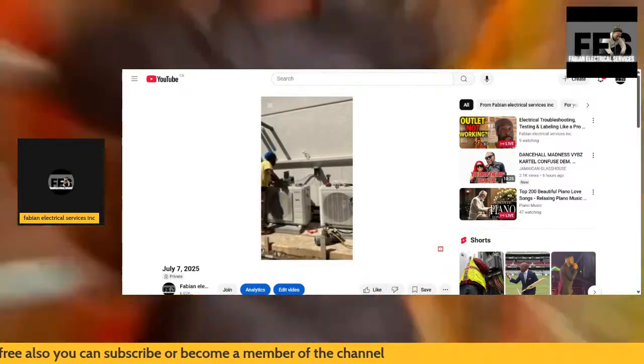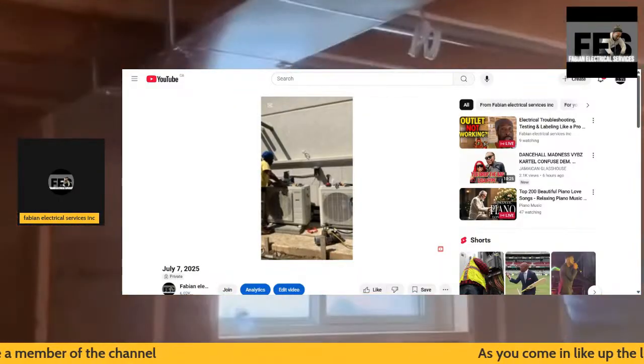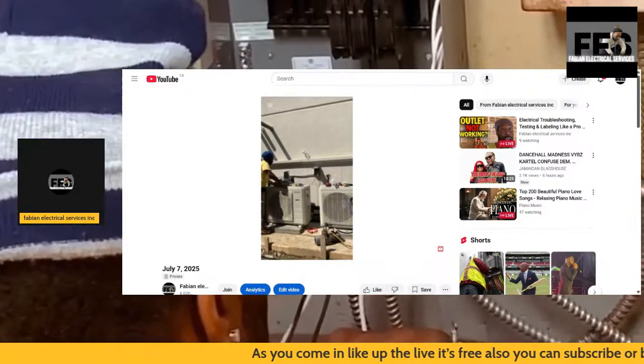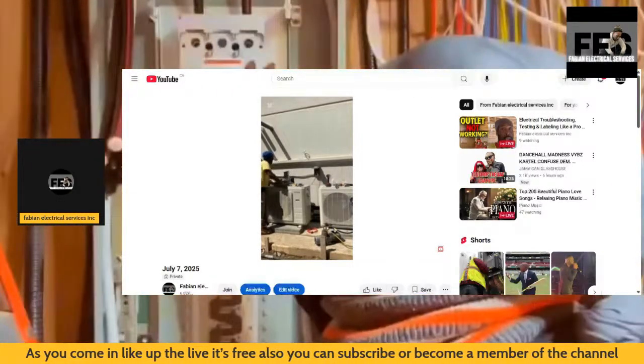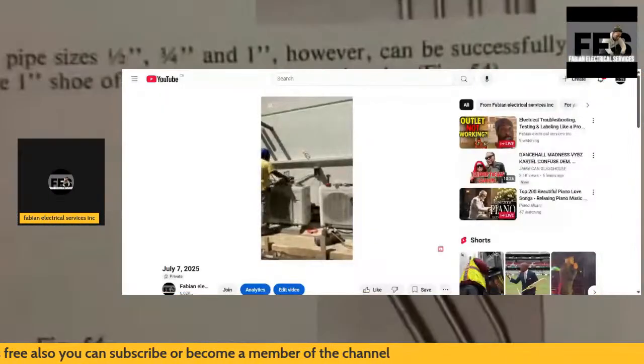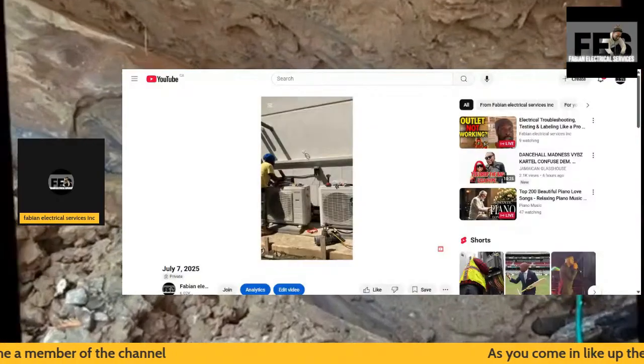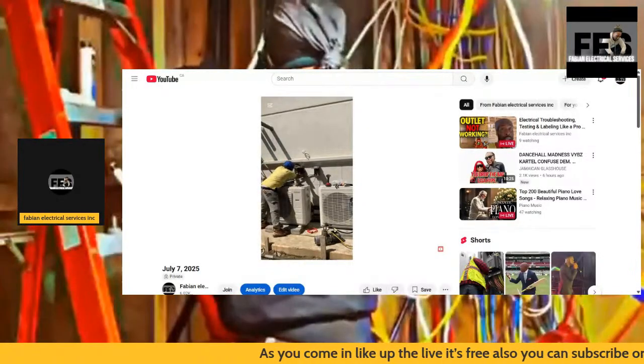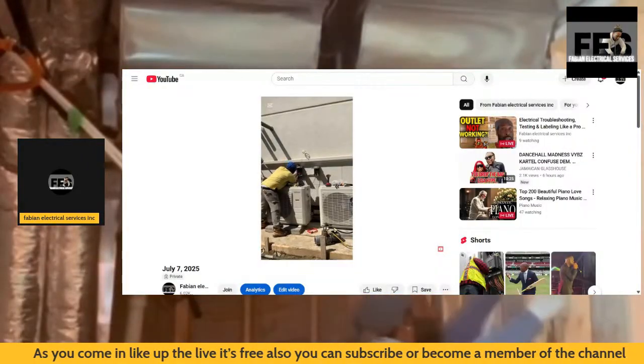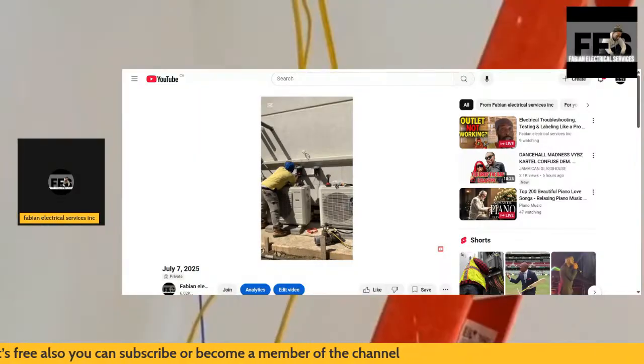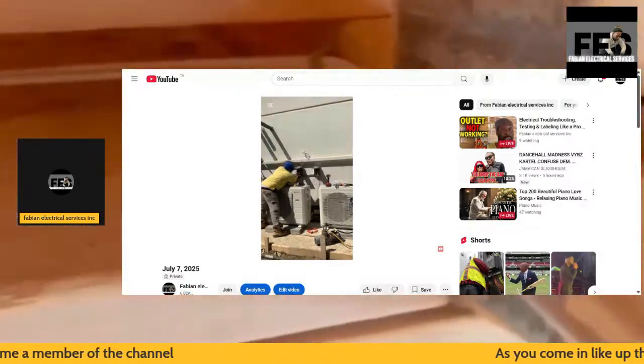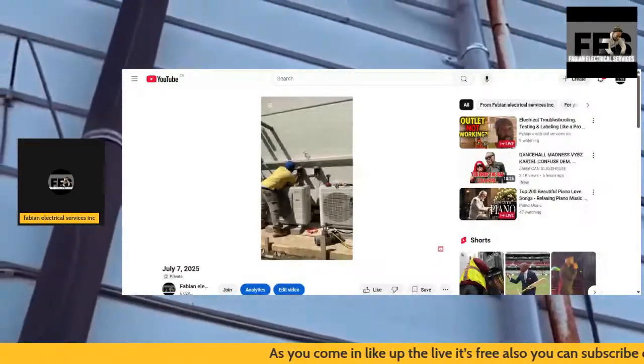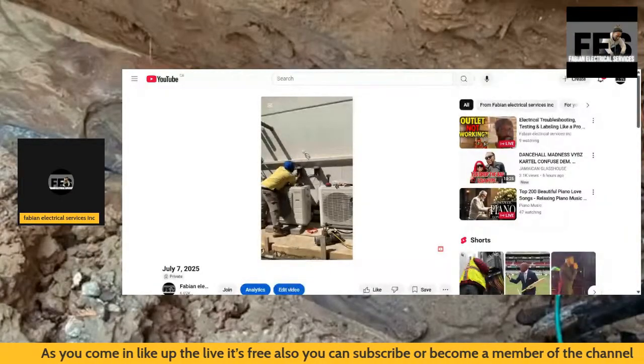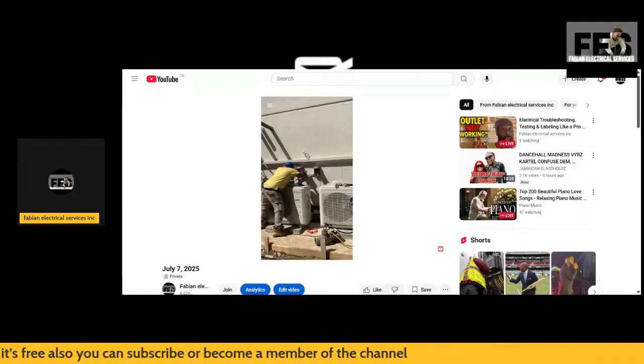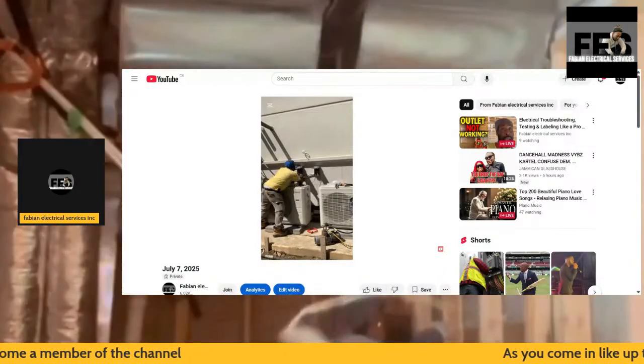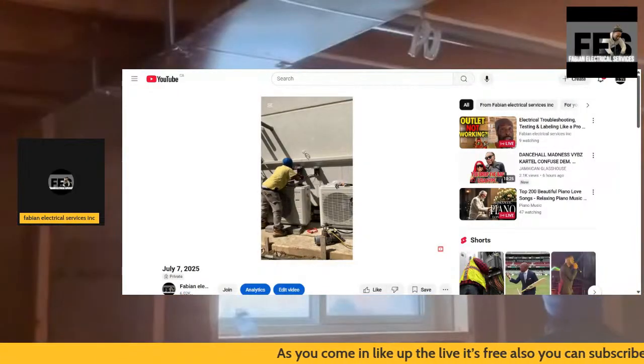This is an installation of electrical conduit, a 60 amp non-fusible disconnect. The disconnect is rated for 60 amps, and the size of the air conditioner unit is 20 amp, 2 pole. I'm going to be using liquid tight connectors so that my conduit is protected outdoor from rain and water getting into the disconnects themselves, which has to be protected. For that reason, I'm using liquid tight conduit in this installation.